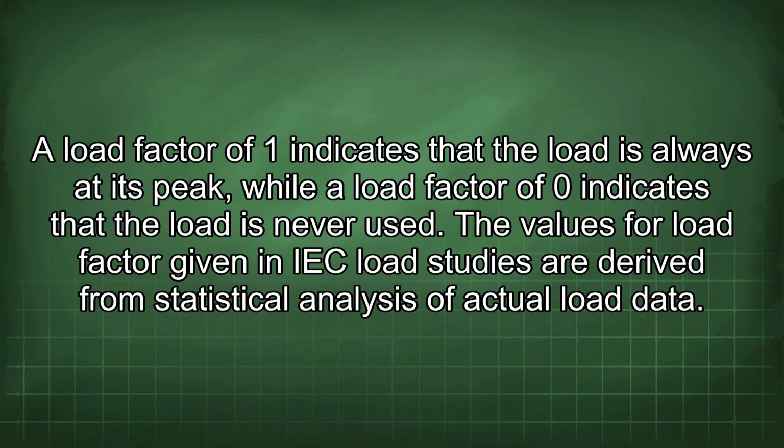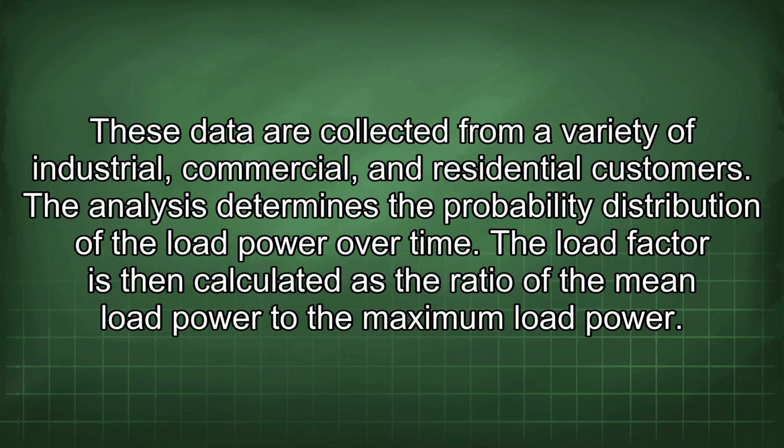The values for load factor given in IEC load studies are derived from statistical analysis of actual load data. These data are collected from a variety of industrial, commercial, and residential customers. The analysis determines the probability distribution of the load power over time. The load factor is then calculated as the ratio of the mean load power to the maximum load power.